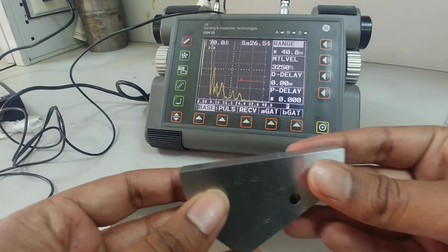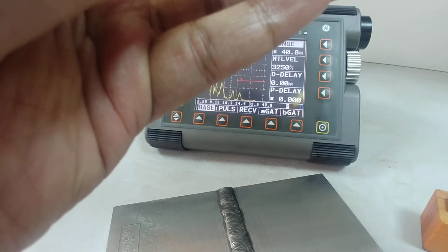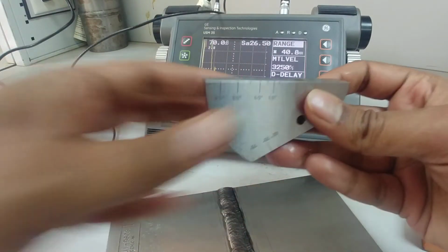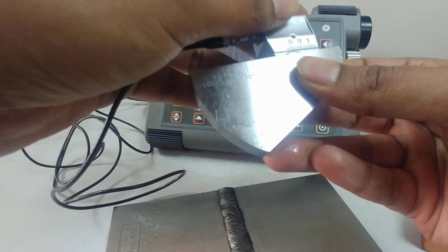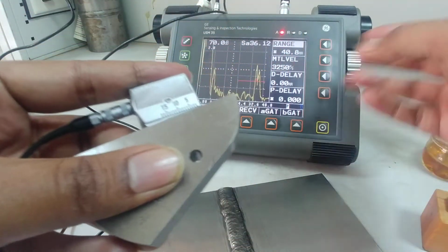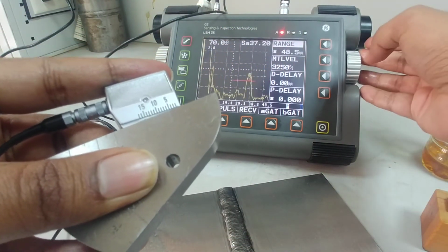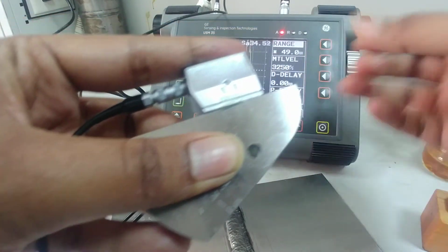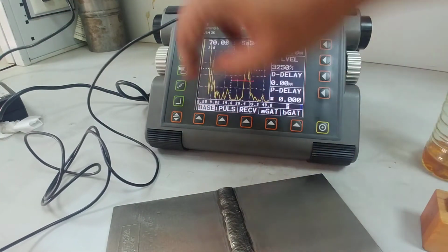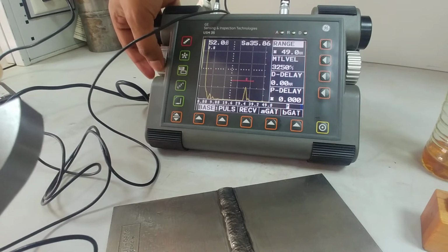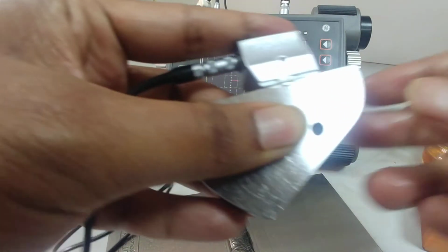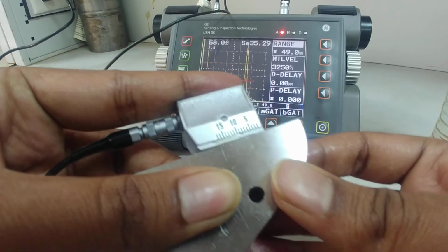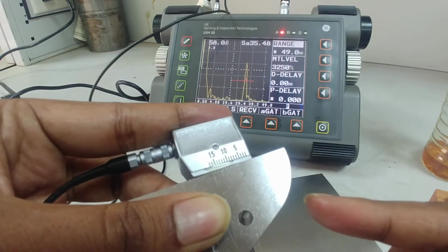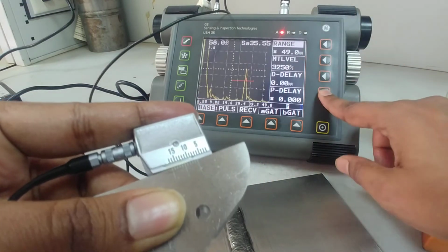And you have an index point, just put some oil on the index point, just put it over here. You can actually find the peak. Let me just increase the range. Yes, you can see. Gain value is too high. Okay, that's good. Now I'm just trying to find the peak value. So this is the peak, and the value should read as 25, but it's showing 35.